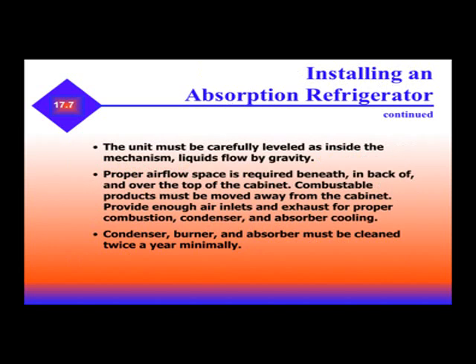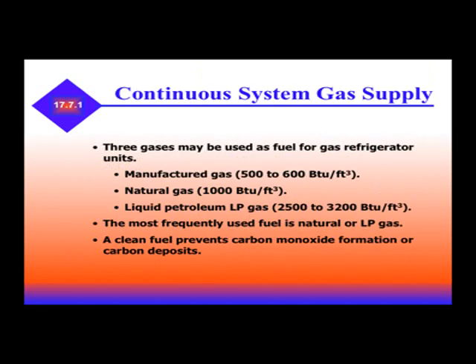The unit must be carefully leveled, as liquid flows by gravity. Proper air space is required. Combustible products must be moved away from the cabinet. Make sure you have enough air inlets and exhaust for proper combustion, condenser, and absorption cooling. The condenser, burner, and absorber must be cleaned at least twice a year.